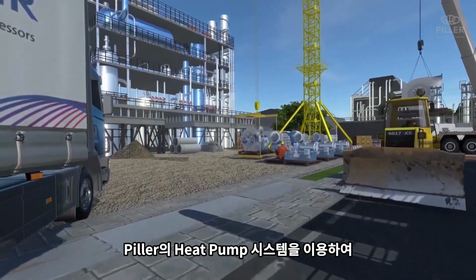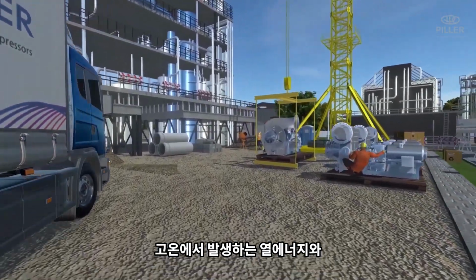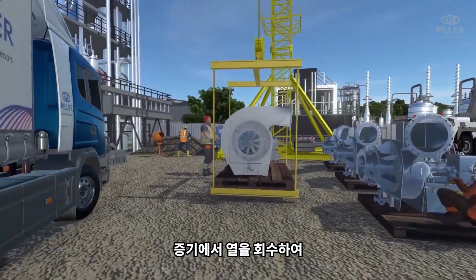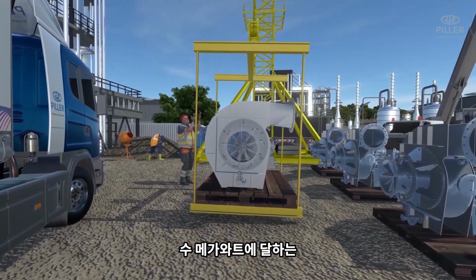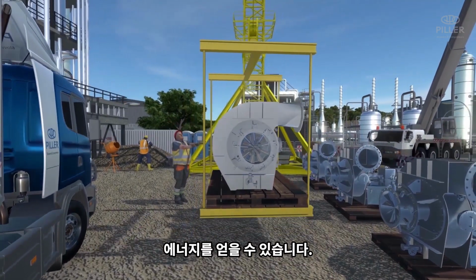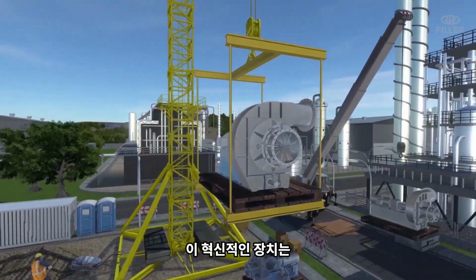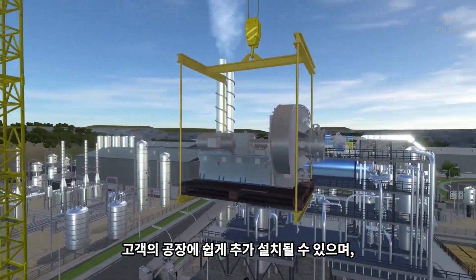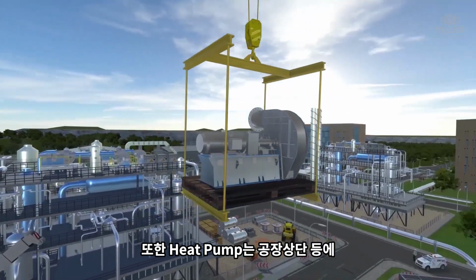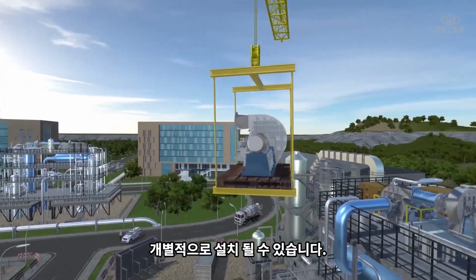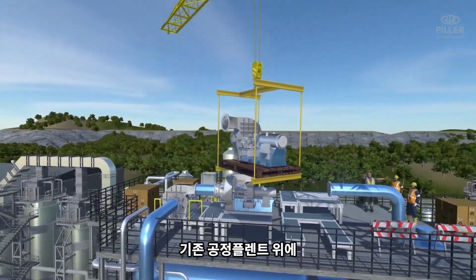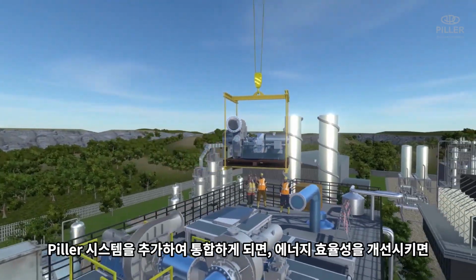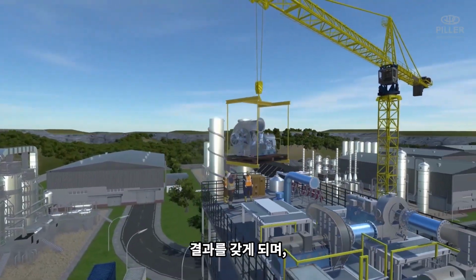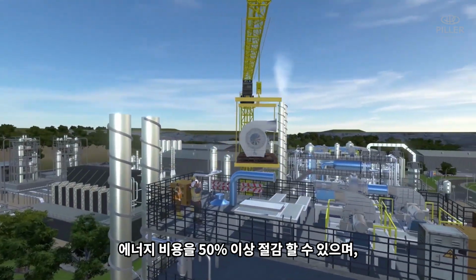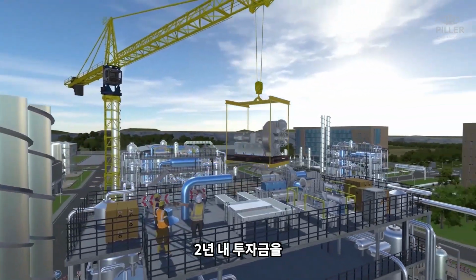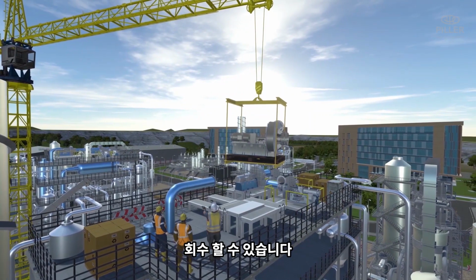Our heat pump system is the ideal solution for heat recovery in these process industries, providing several megawatts of thermal energy and steam at high temperatures. This innovative system is perfectly suited for retrofitting existing plants. The components of the heat pump can be placed individually, for example, on platforms above the existing process plants. The integration of our system and the resulting improved energy efficiency saves energy costs by more than 50% and leads to project payback periods of less than 2 years.